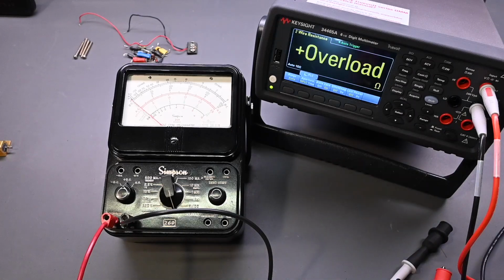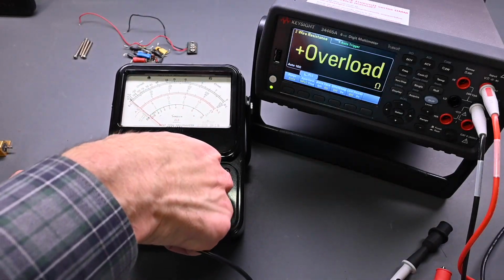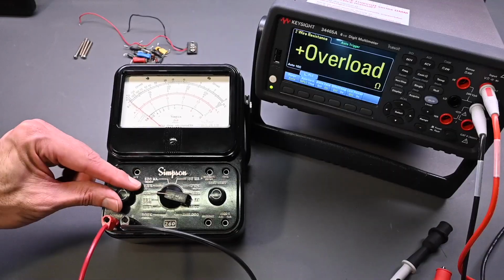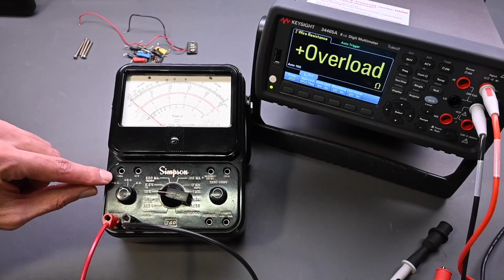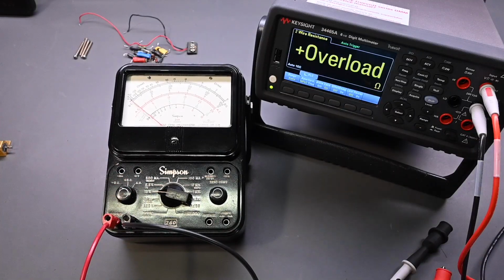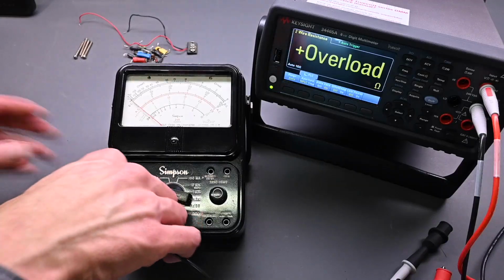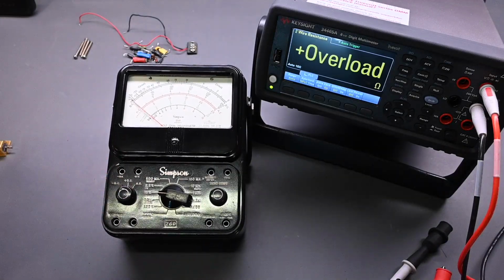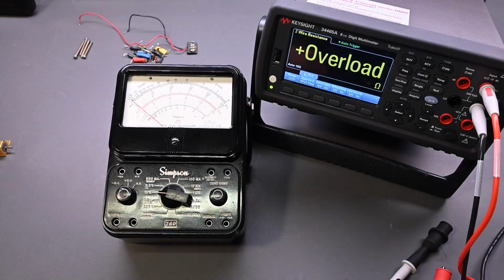And going back to a voltage measurement, if I go over here, let's go to 10 volts. But I'll put this on the minus DC. I hadn't tried that range yet, just to make sure the switching is working correctly. So I'll just disconnect these leads right here. And I have 10 volts set on the Keithley 236. Let's just plug that in here.